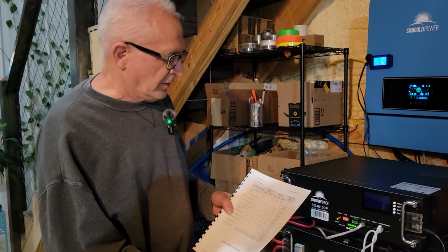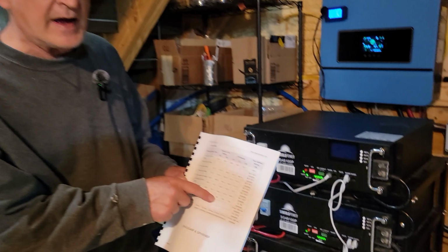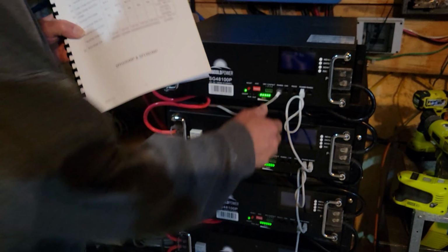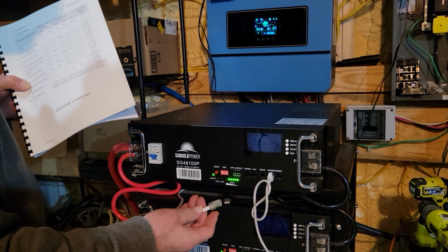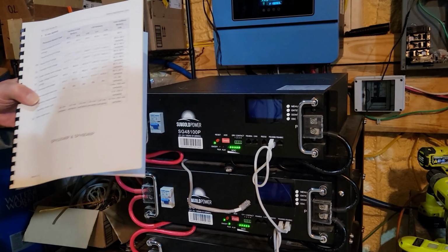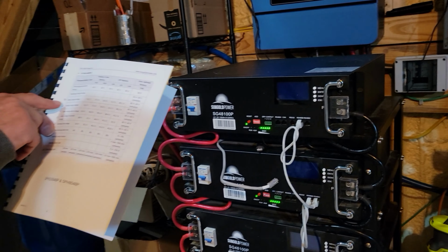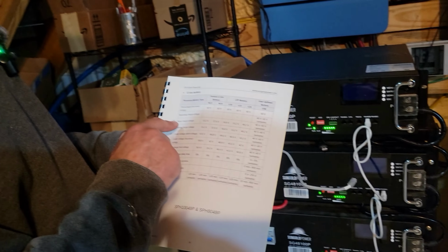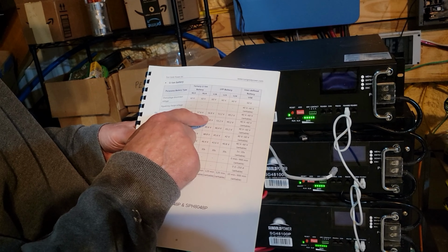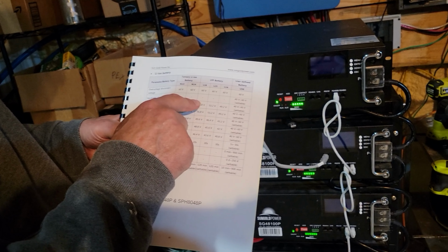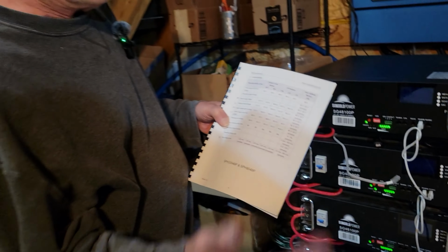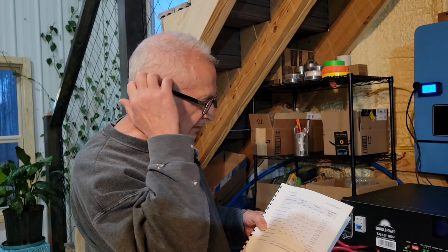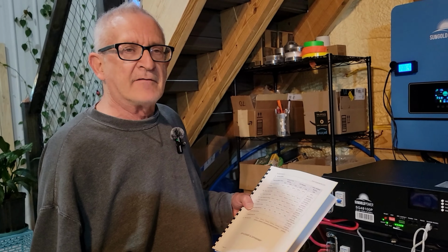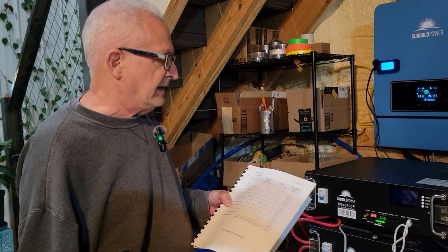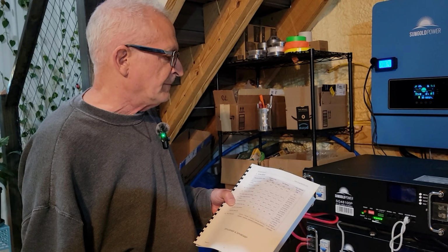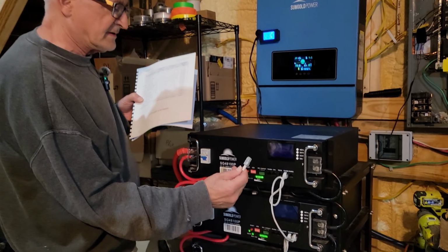When you're setting up the user battery type to match these parameters, it's important that you pull the data communications cable first. If you don't do that, some settings, like boost charge and floating charge voltage, you have to change to 58.4. It'll change it, but if you navigate away and come back, it'll revert to whatever the default was. That's okay for normal operation, but for calibrating, you need it at 58.4 volts, and the only way to do that is to pull this data cable.